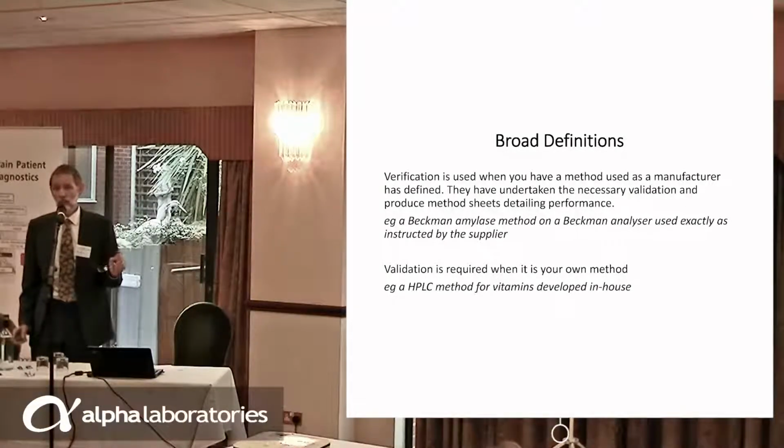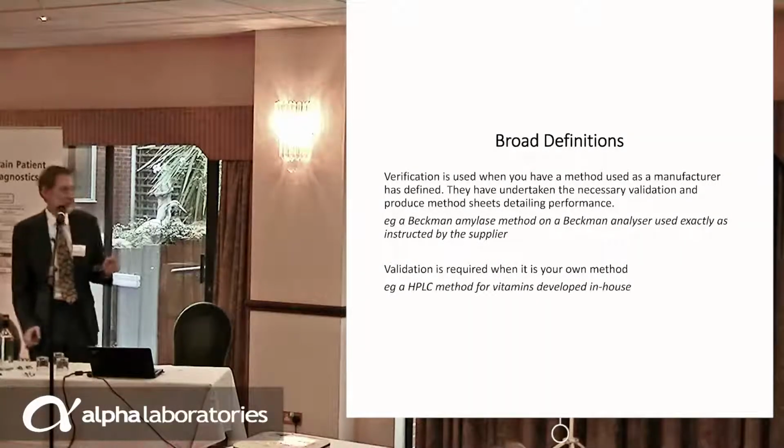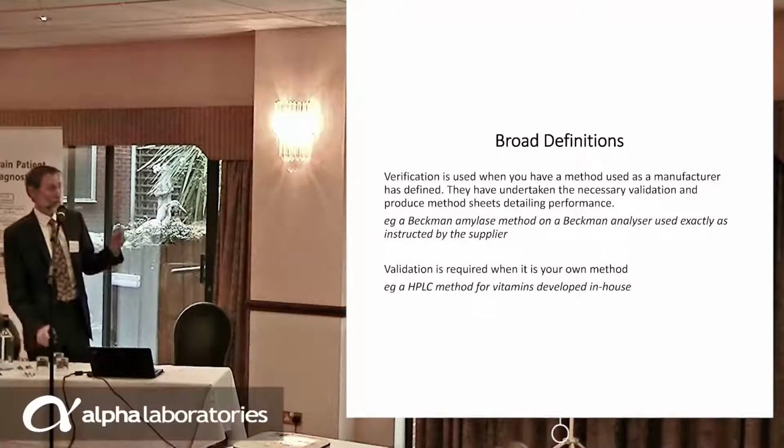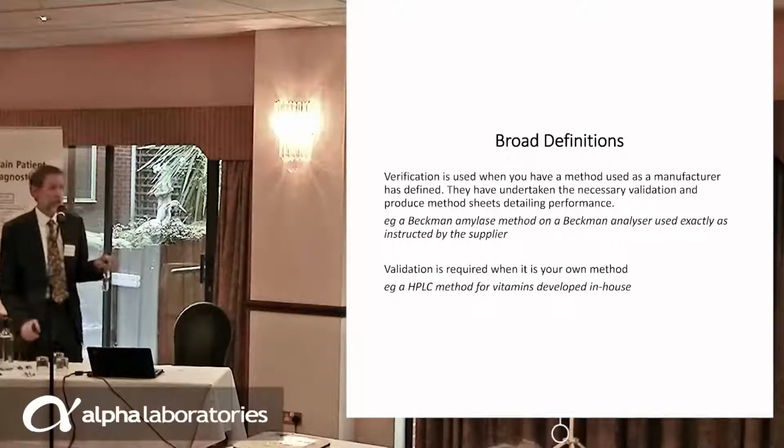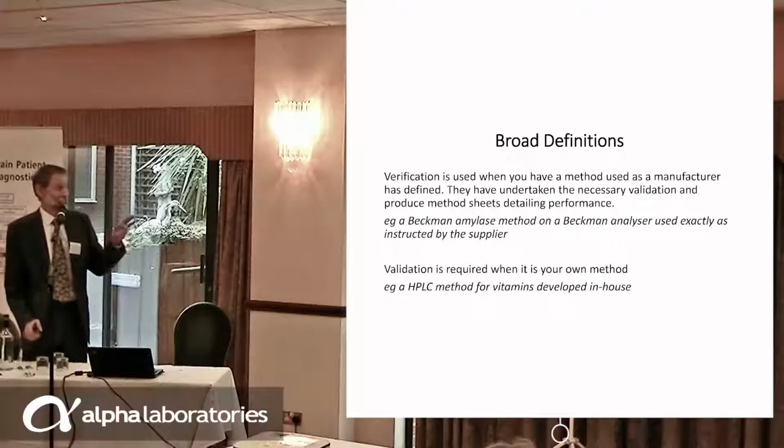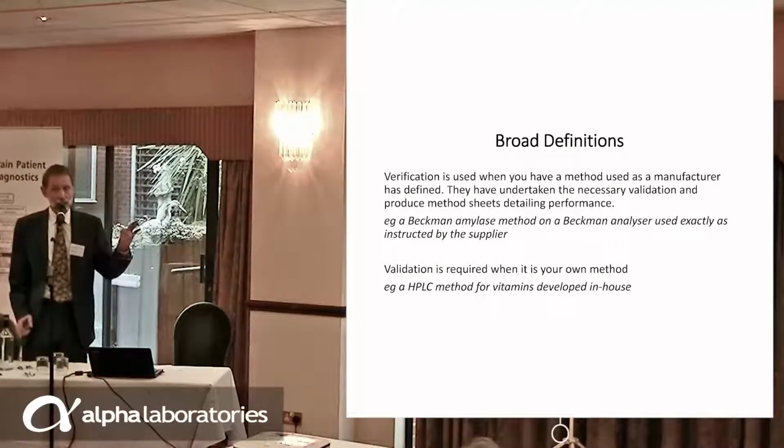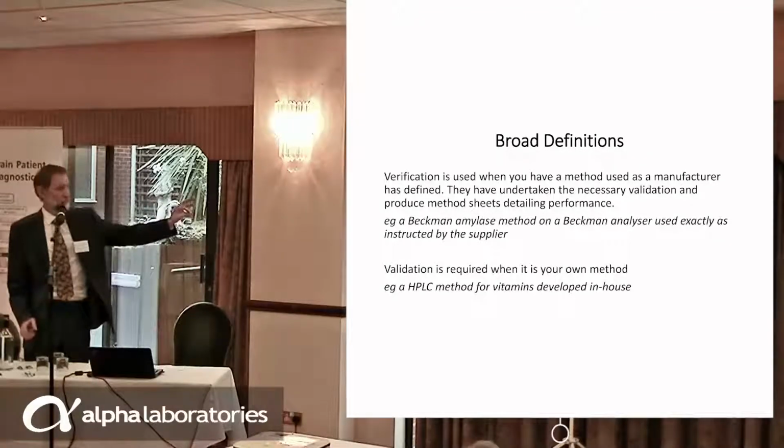You don't have to repeat all of that validation work, but you need to verify that in your hands it is performing in the same way that Siemens think it should be performing. So, for example, a Beckman method on a Beckman analyzer used exactly as the supplier has instructed. Okay, that would be a verification.